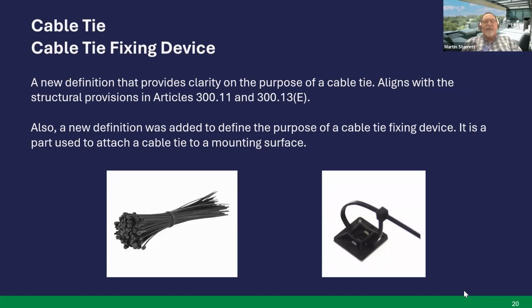Cable tie and cable tie fixing device. A new definition that provides clarity on the purpose of a cable tie, aligns with the structural provisions in Article 300.11 and 300.13E. We'll also see as we go along this month some new listing requirements that have been added for cable ties. Cable tie fixing device, it's a new definition that was added to define the purpose of a cable tie fixing device, and that is a part used to attach a cable tie to a mounting surface. Next slide.